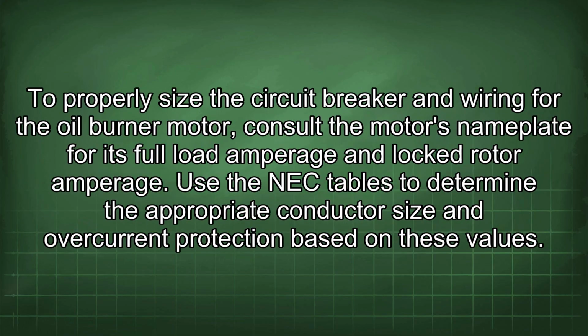To properly size the circuit breaker and wiring for the oil burner motor, consult the motor's nameplate for its full load amperage and locked rotor amperage. Use the NEC tables to determine the appropriate conductor size and overcurrent protection based on these values.